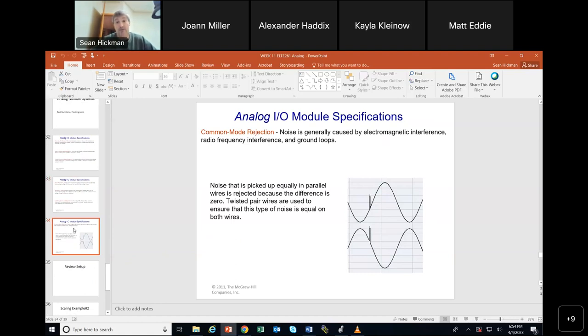Common mode rejection. Remember that noise, when the signal's coming down the line and we're doing analog, the resolution is very high, so any little change in there is going to be recorded and it's going to affect our answer. A lot of times noise is picked up equally in parallel wires. The engineering in there is made to reject that. Okay, twisted pair wires are used to ensure that the type of noise is equal in both wires, and therefore it can be sensed and then rejected.